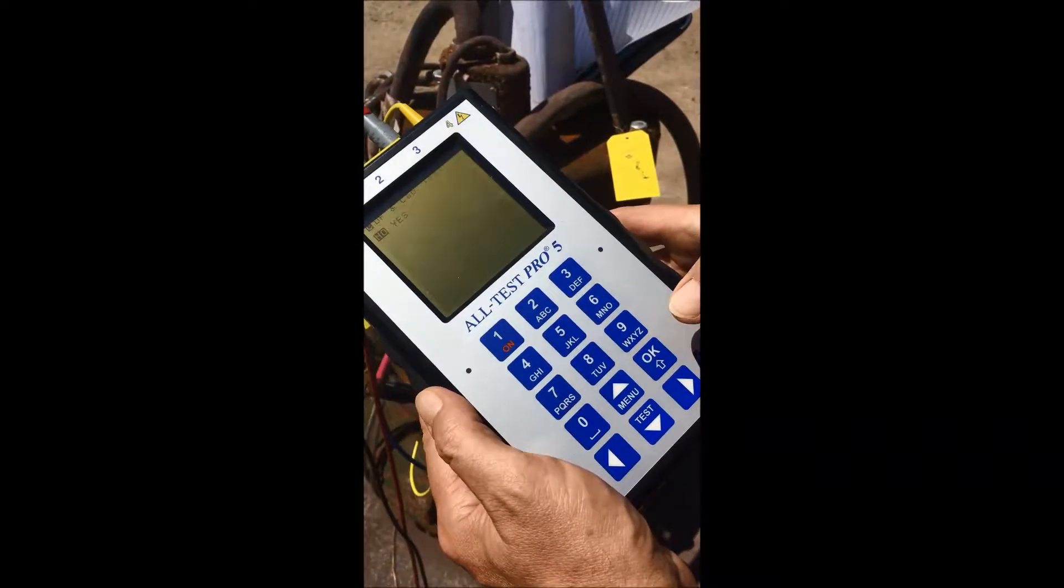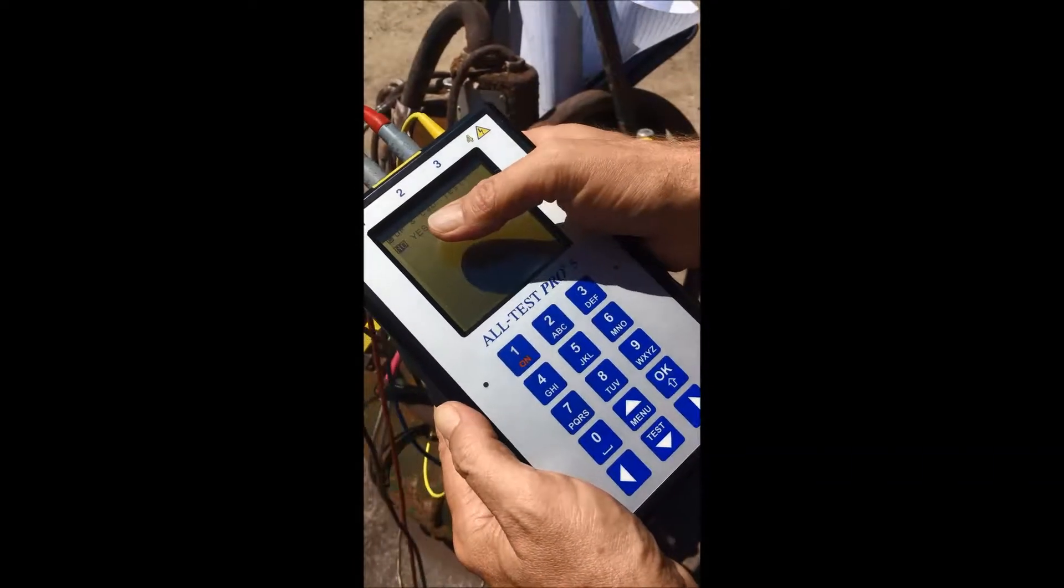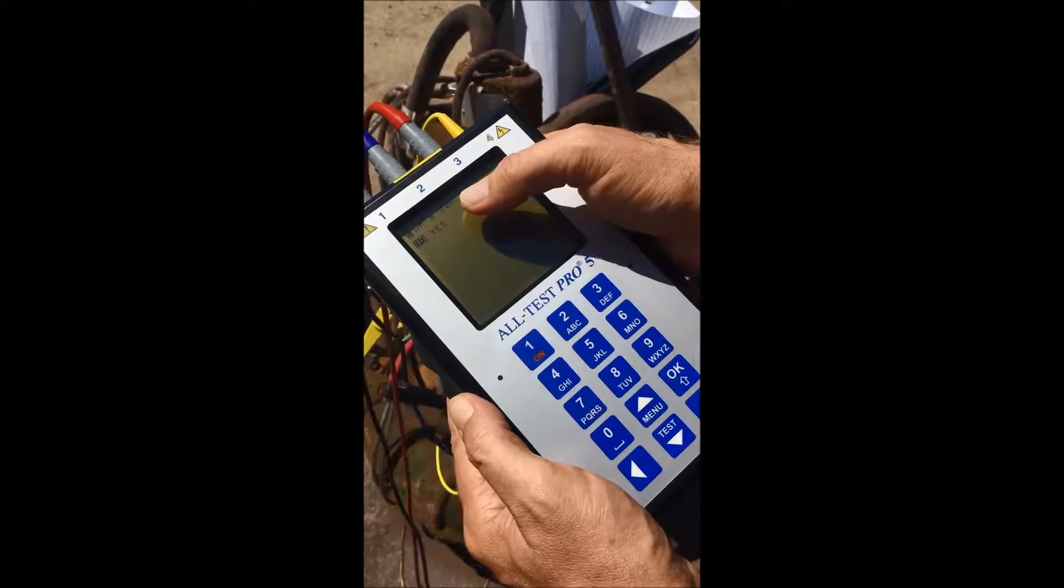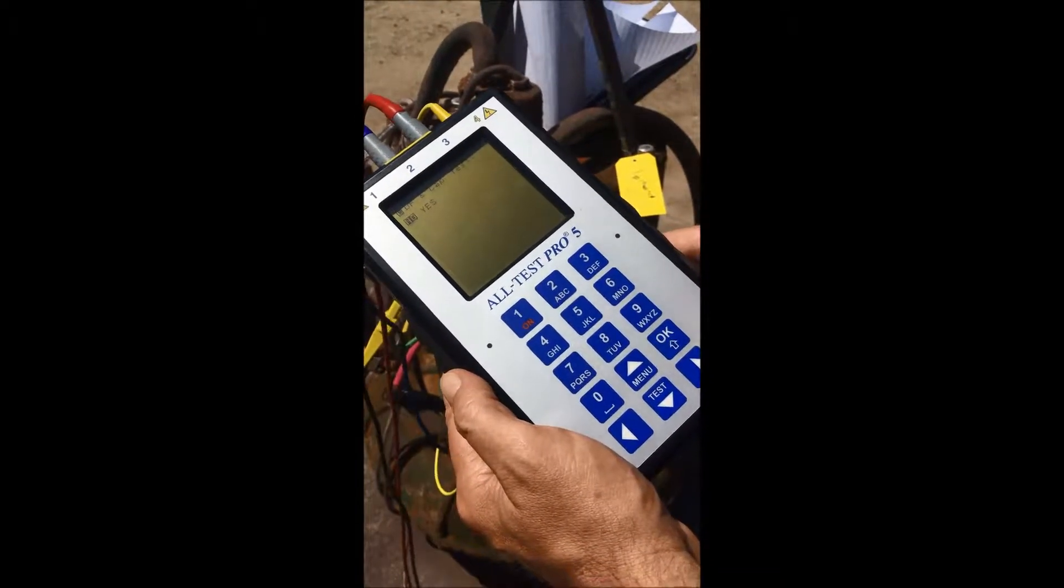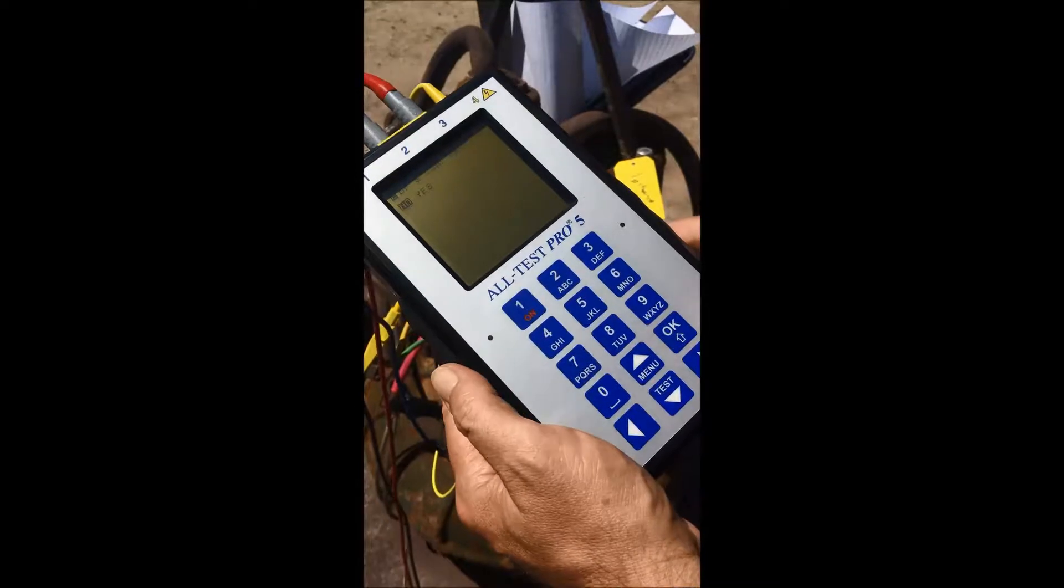We're looking pretty good and it is now telling us hit OK to continue. It's going to walk us right through what to do. We're going to run a dissipation factor and capacitance test. That is going to pick up on winding issues. Something that a megger and a multimeter does not do for you.